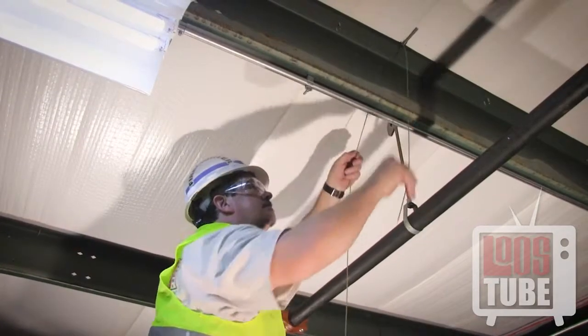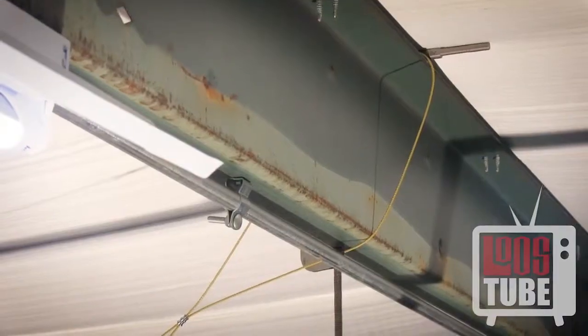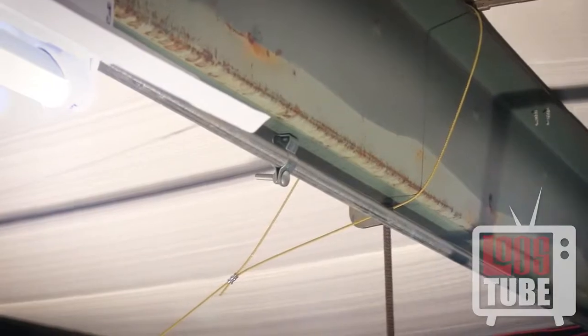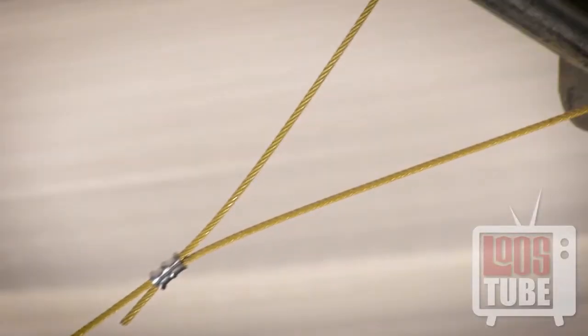The first method of attaching to the structure is wrapping the cable around a steel beam or the top or bottom chord of a bar joist, then swaging an oval sleeve. Be sure to avoid swaging the sleeve too close to the joist. The angle maintained by the loop should be less than 45 degrees.